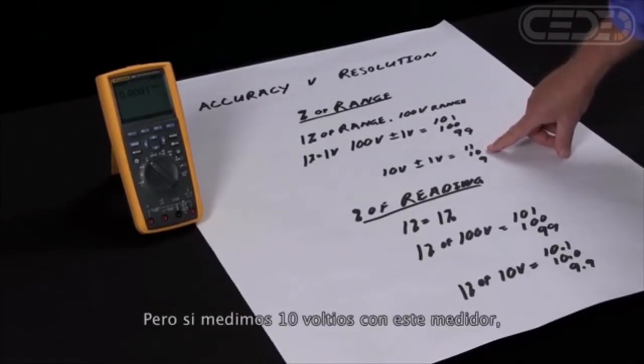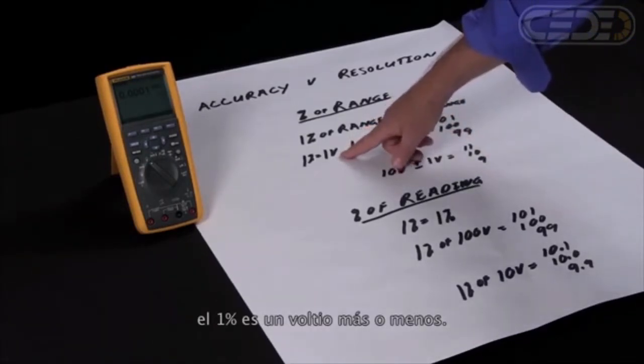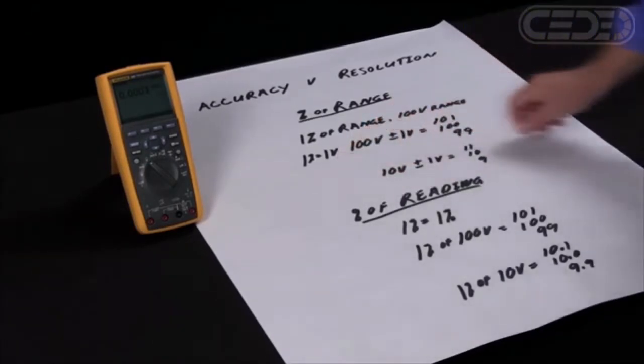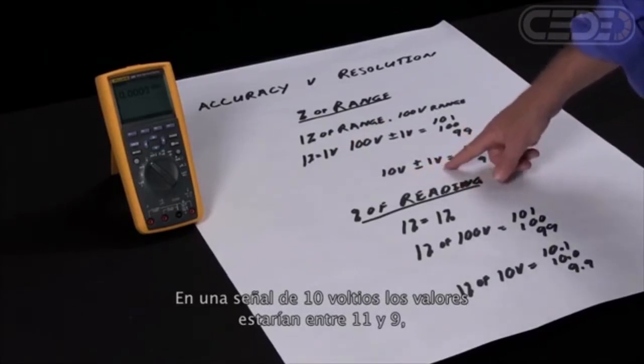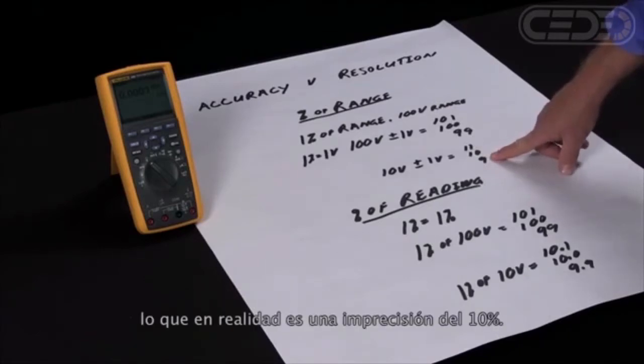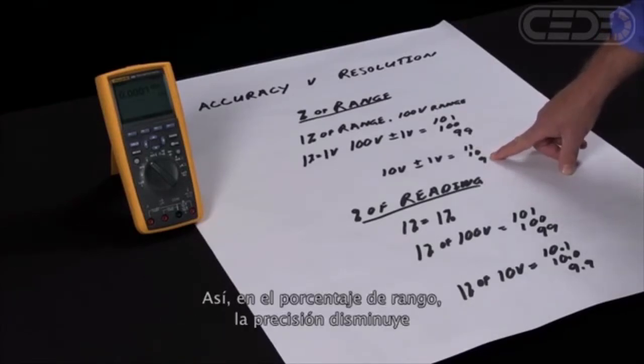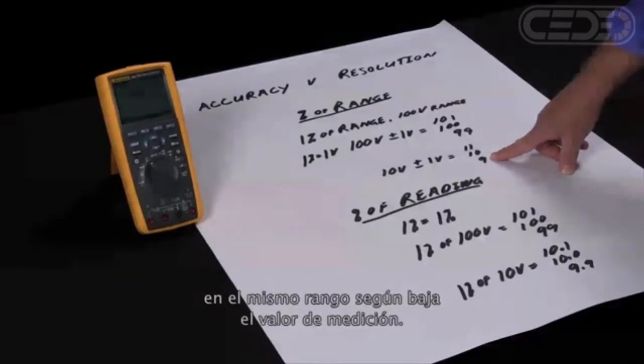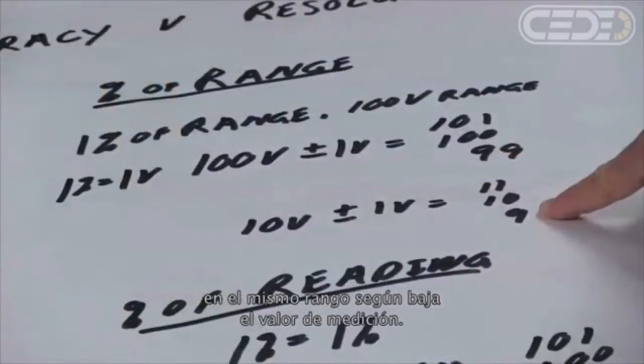But if we're measuring ten volts on this same meter, the one percent is plus or minus one volt. On a ten volt signal, plus or minus one volt gives us between nine and eleven, which is actually an inaccuracy of ten percent. So with percent of range, the accuracy actually decreases on the same range as you go down with the measurement values.